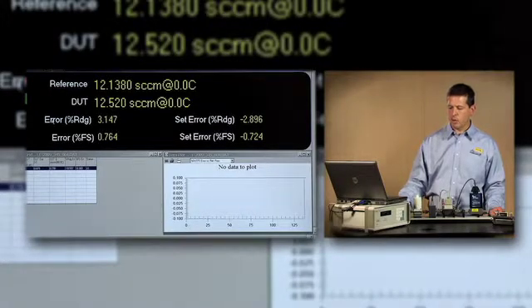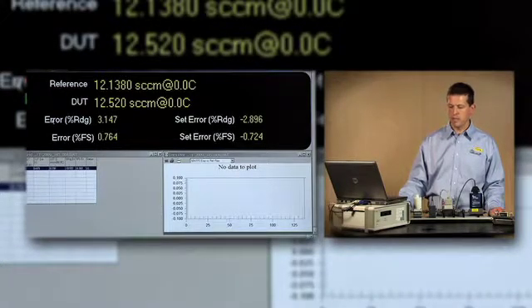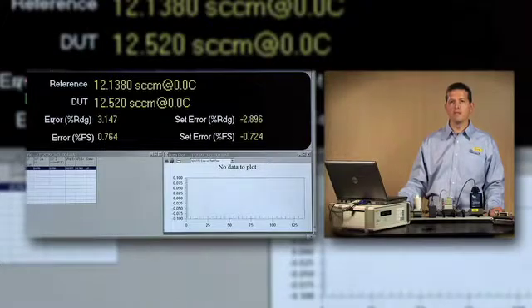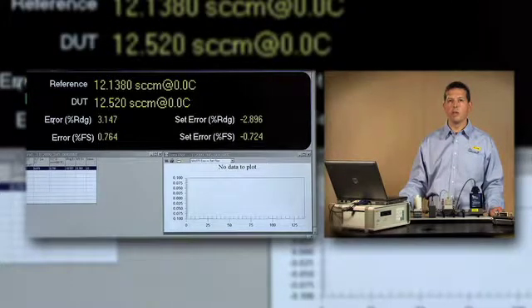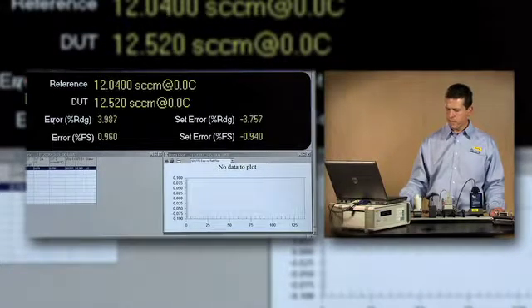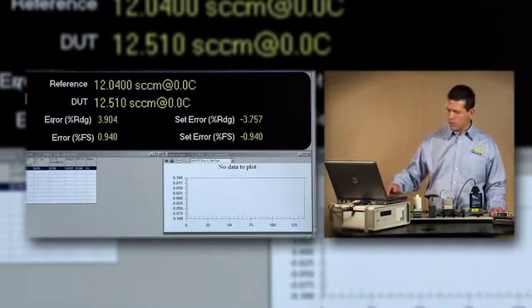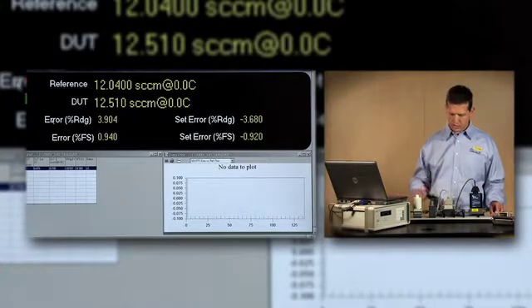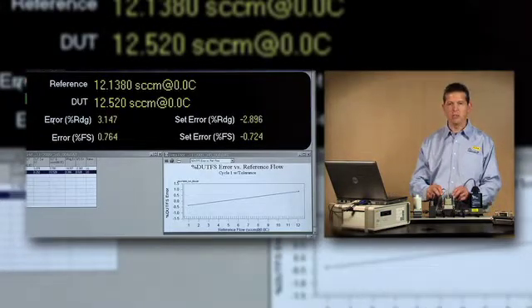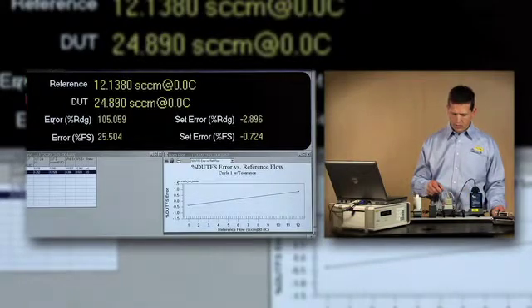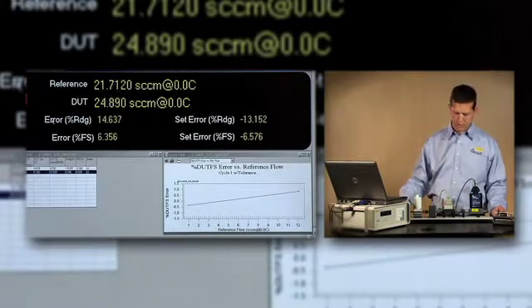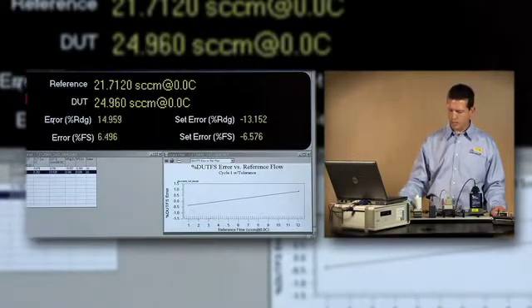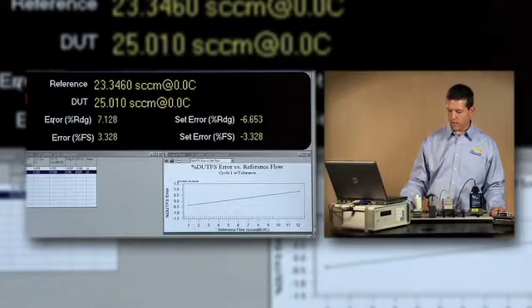And then this Molbox One Plus, which is a replacement or update for a very popular Molbox One terminal that has been on the market for some time. During the test, the Molbox One Plus is going to measure both the upstream and downstream absolute pressure and also the absolute temperature coming through that cable off of the mole block to calculate flow.